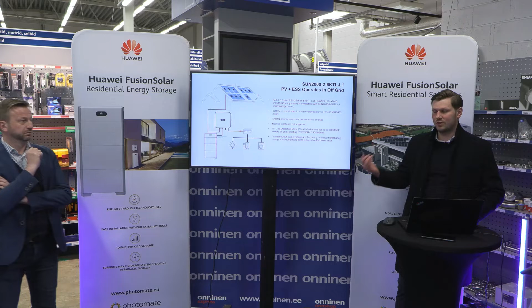Yes, it's a very common question, but you cannot simply connect the diesel generator straight to the AC here, because there are two issues. You cannot use both sources at the same time — you have to use either the generator or PV at one time. There are special products, special switches, which we also offer, that allow the system to work like this. But if you connect the diesel generator directly, there's a risk you'll harm the generator or the inverter, because current might flow not to the load but straight to the inverter and damage the input. So that's how it works.